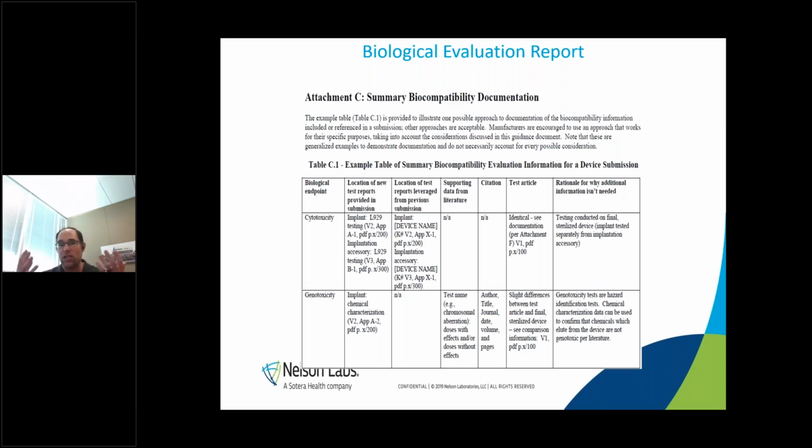It could be a change justification, whatever you want to call it, but it's that story you have to walk through, because if not, they can get lost in the details. And let me tell you, I've been on so many FDA calls with simple changes that turned into huge fiascos because we didn't just simply walk through the change with them to help them understand that the change is low, the risk is low to the medical device.